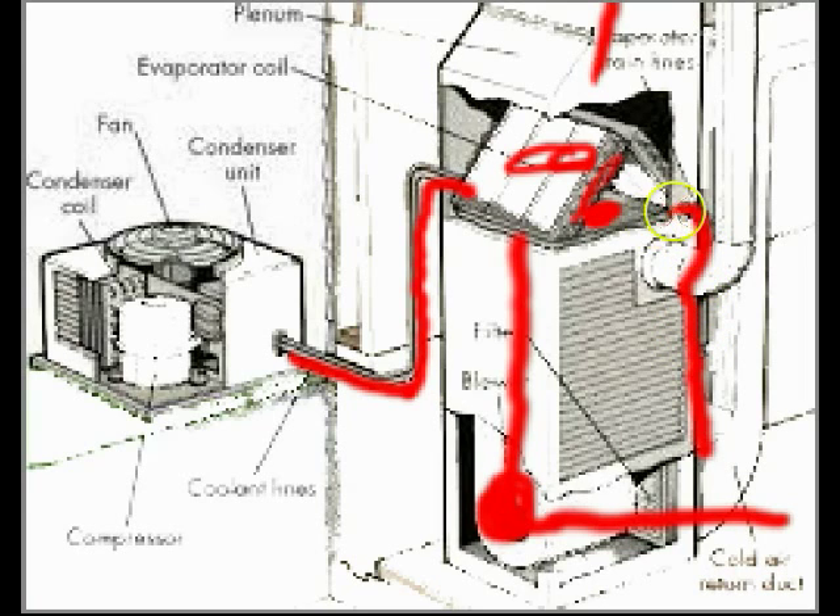But if people do not change their filter, eventually dirt and debris, dog hair, cat hair — that sort of thing — will get caught in this and it will block up and overflow, and that's bad. That's why a lot of times if this is in the attic you'll have a catch pan underneath here, and then it will have a drain that goes out by a window or something. If you ever see that draining out by a window, you know your primary line is clogged.